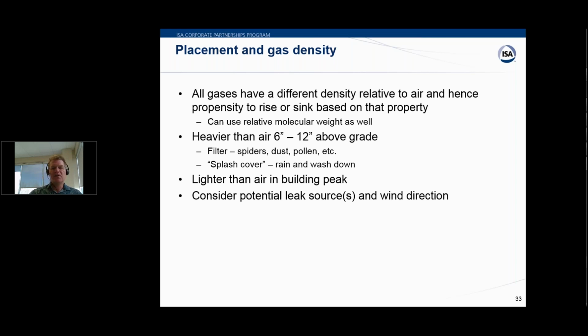So if your gas is heavier than air, such as H2S, hydrogen sulfide, you typically mount your detectors 6 to 12 inches above grade. And every gas detector will have a little filter, keeping spiders, dust, pollen out of getting to that membrane, or in the case of IR, to the path. And typically that cover will also be a splash guard, especially for the ones at grade, because there's rain and people hosing and washing down the plant, that kind of stuff.